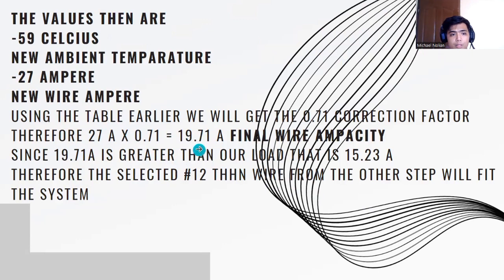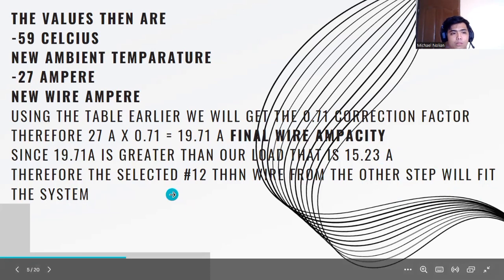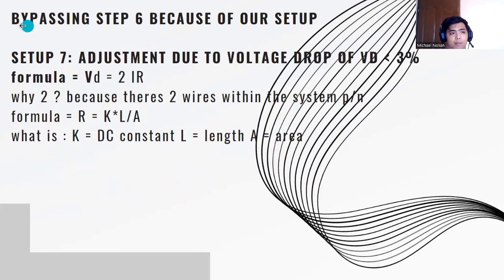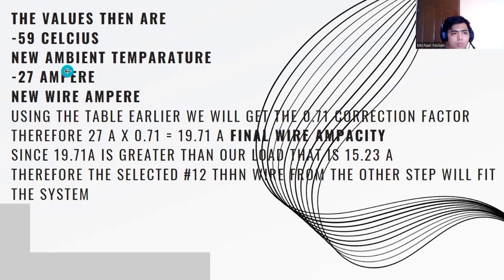So it will equal 19.71 ampere. This is now our final wire ampacity. Since 19.71 ampere is greater than our load, which is 15.23 ampere, therefore our selected number 12 thermoplastic high heat resistant nylon coated wire from the other step, which I think was from a different reporter, will fit the system. Furthermore, we will bypass step 6 because of the setup we have, where the wires are short.